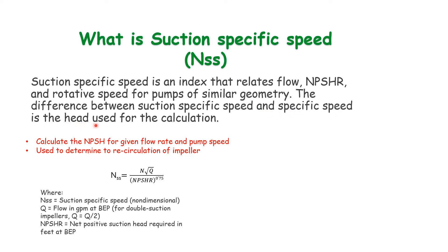The difference between suction specific speed and specific speed is the head used for the calculation. Both have similarities, but the difference is that in specific speed we use the head for calculation, whereas in suction specific speed we use the NPSHR.